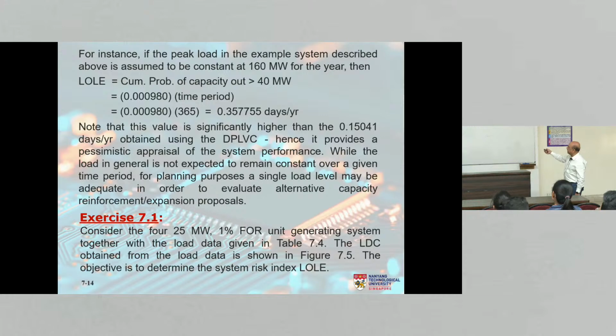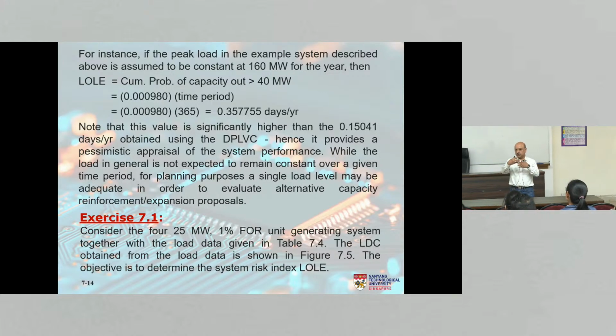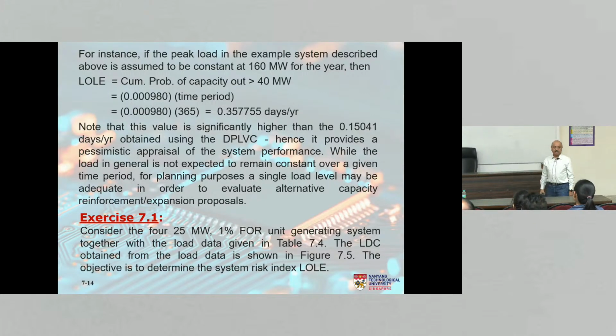So while the load is not expected to remain constant, for planning purposes, a single load level may be adequate, especially when you are comparing alternative strategies, alternative options. That's all I'm saying. So you have the option. If you want to consider the load curve, which is so uncertain in the future, you can do it. Alternatively, just use a constant load level. You get an idea of what kind of risk will exist in the system. It may be a pessimistic appraisal, but isn't pessimistic better than optimistic? Because the load is likely to be much more than what you are expecting it to be, isn't it? So we are better off with a pessimistic appraisal in many ways.